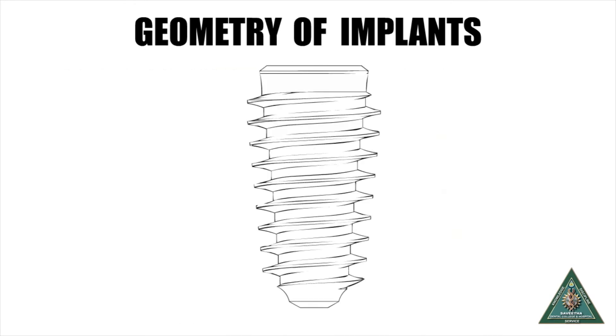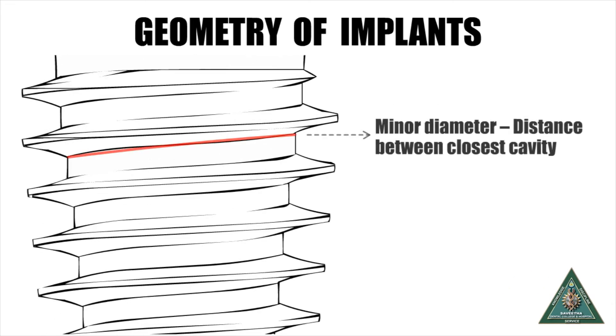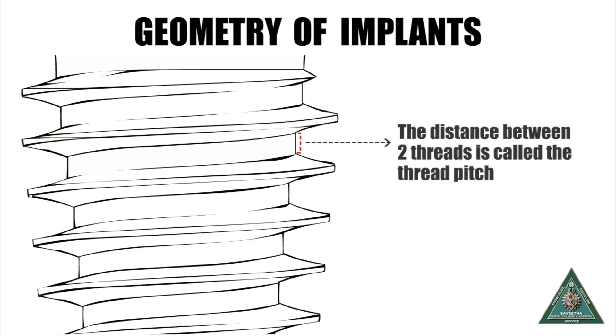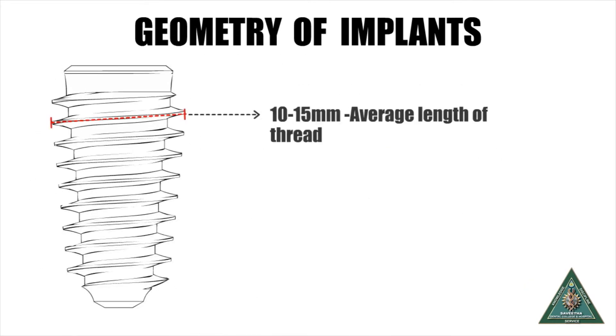The body of implants has threads which can be continuous or interrupted. The geometry of implants is manufactured with extreme precision. The width of the implant at the base of the thread is called the minor diameter, whereas the width at the apex is called the major diameter. The distance between two threads is called the thread pitch, which is usually 1 millimeter.